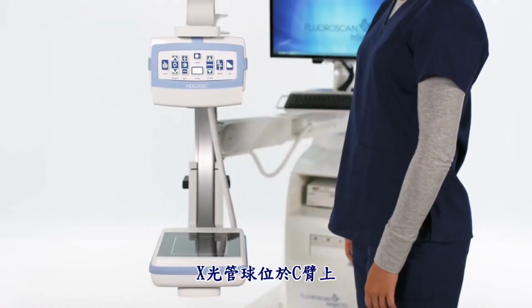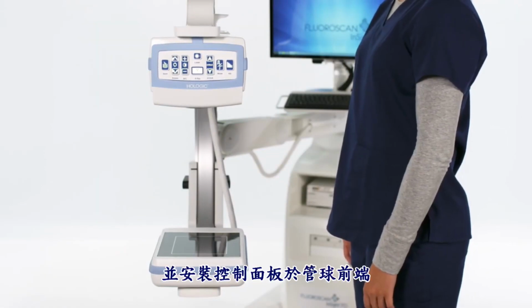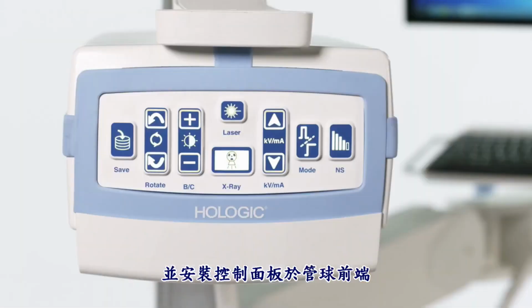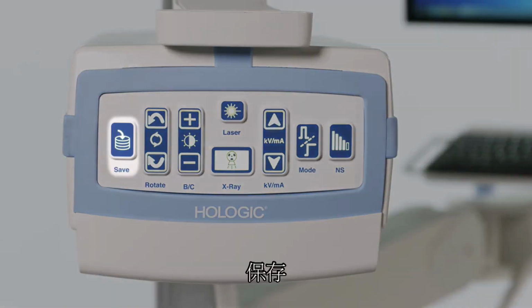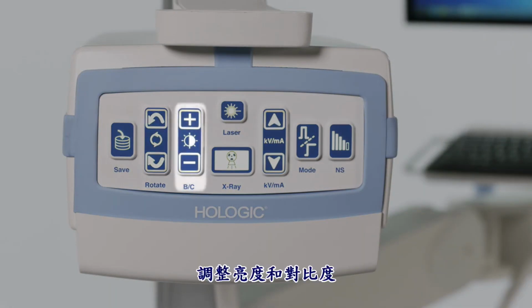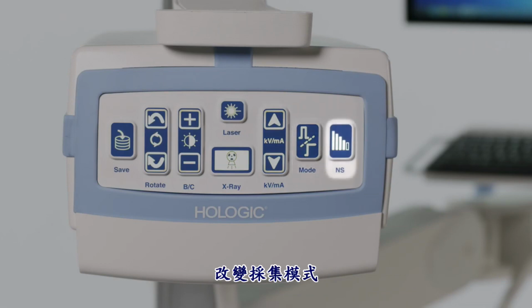The X-ray source is located on the C-arm and houses the sterile field controls. These sterile field controls have the option to save, rotate, adjust brightness and contrast, take an X-ray, adjust KV and/or MA, change acquisition mode, cycle through noise suppressions, and turn on the laser.